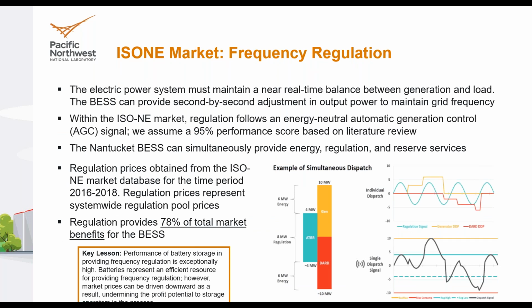There are three components to this. There's a capacity component, where you can bid in the full range of the capacity of the unit. For a generator, effectively you're taking a midpoint and cycling up and down around that midpoint. But an energy storage system can provide at least twice the regulation capacity, because you have full regulation up and full regulation down, since you can be either charging or discharging the battery system.